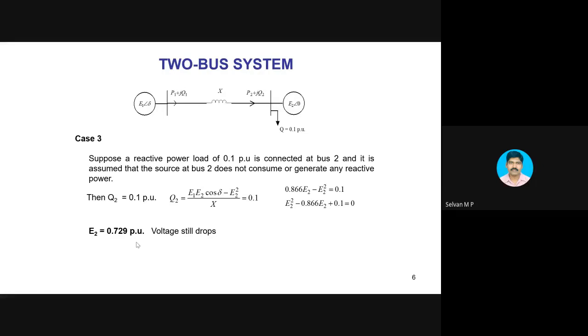Earlier it was 0.866, now it has dropped to 0.729. Why? I have connected a reactive power load and the source near this load is incapable of supplying reactive power. So who will supply? The source connected at bus 1 has to supply the reactive power demand of the transmission line and the reactive power demanded by this load. So the total reactive power should come from this generator or this source. That amount of reactive power travels through this line, which causes more current flow compared to case one and case two. And this extra current flow leads to an additional voltage drop, and the voltage becomes 0.729 per unit.